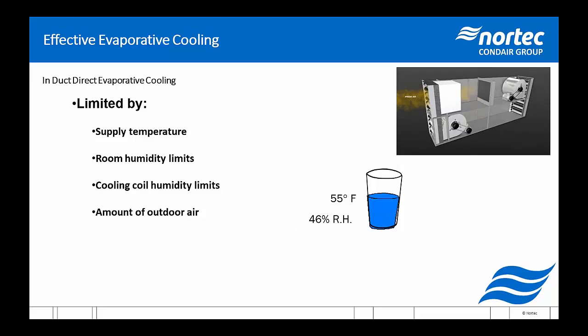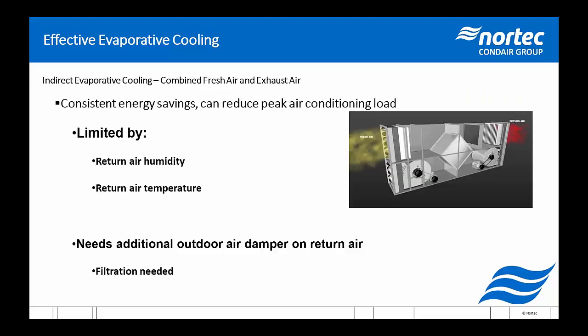That being said, if you have humidification problems, you're generally too humid, this would be my preferred system, and I'd actually do this with a media evaporative system, where we have the return air being humidified effectively to saturation and running through a sensible heat exchanger. And when it makes sense to do, which will be, again, a fair portion of the airside economizer season, we can open up an outdoor air damper to allow more outdoor air into that return air feed and save even more on the kilowatt hour section. So it's a bit of a complicated question. When it comes to in-duct direct evaporative cooling, there is where I choose to use the DL system for its great hygiene, low water waste, and very low pressure drop as well. So basically, I'd use an evaporative humidifier in one situation or another. All of them have their advantages and disadvantages.